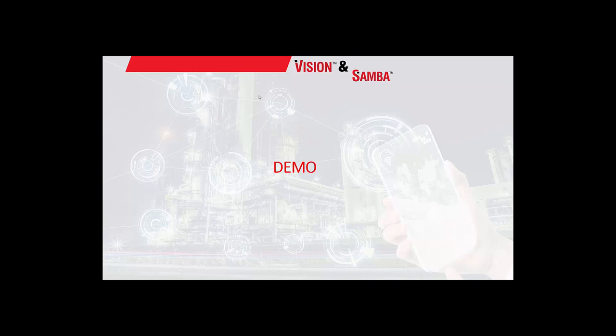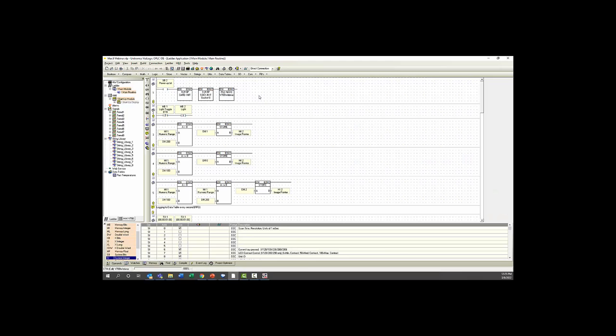For the VisiLogic program, the first thing you're going to have to do is set up the Ethernet connectivity. This must be done using the following blocks, as you see in order in our program here. First, you want it to happen on the power-up bit. You can trigger from any bit, but these should never be running continuously.